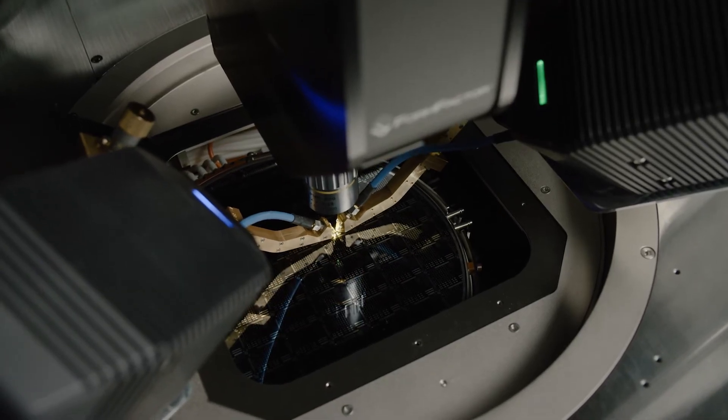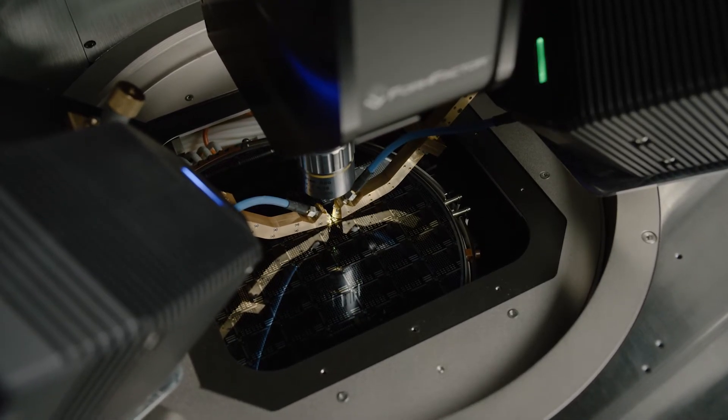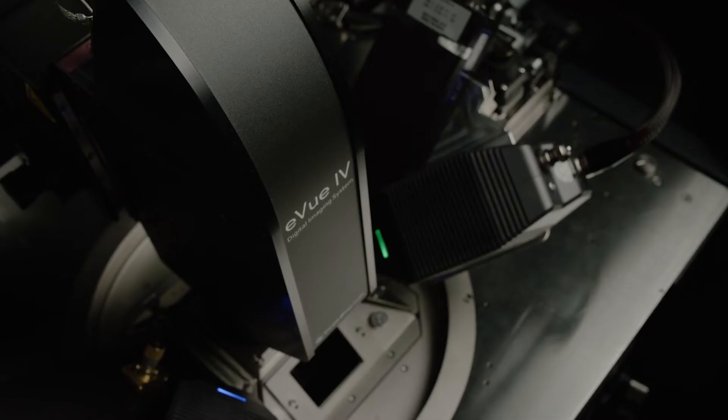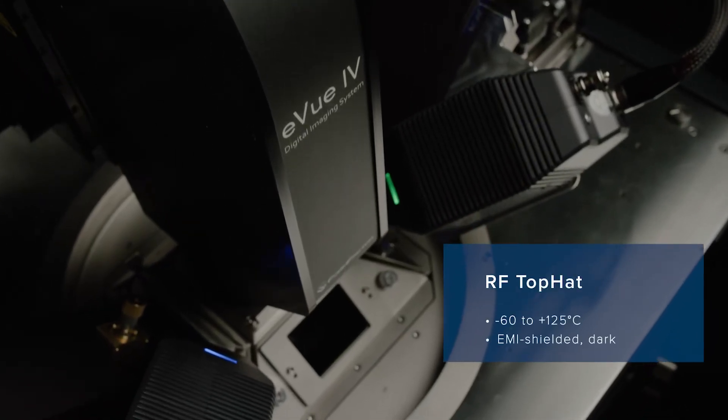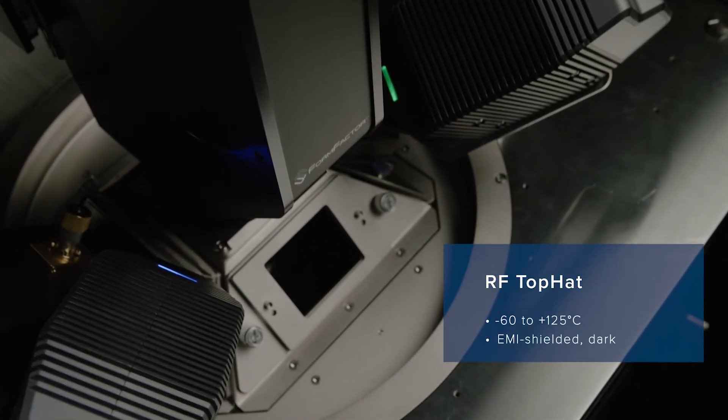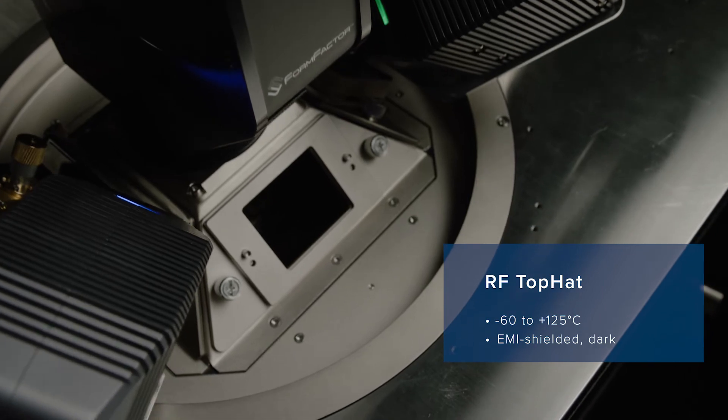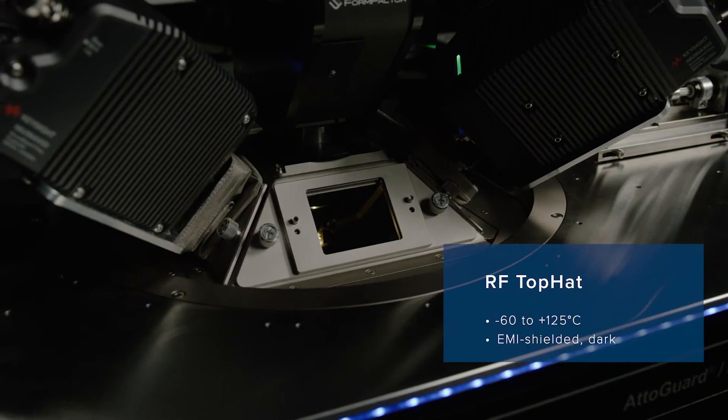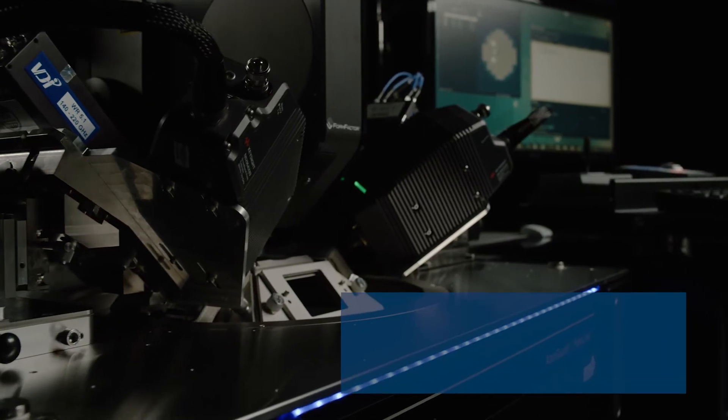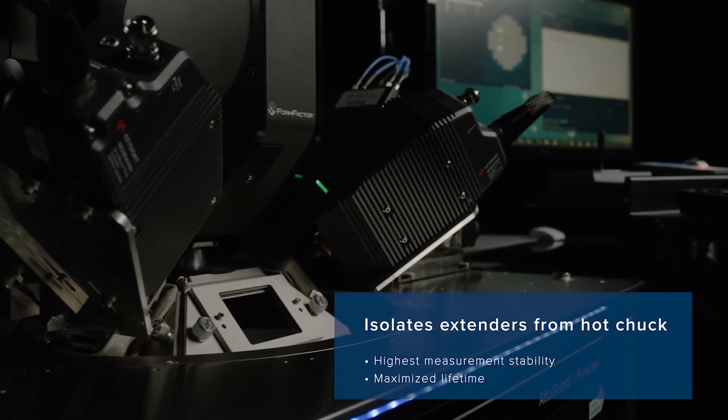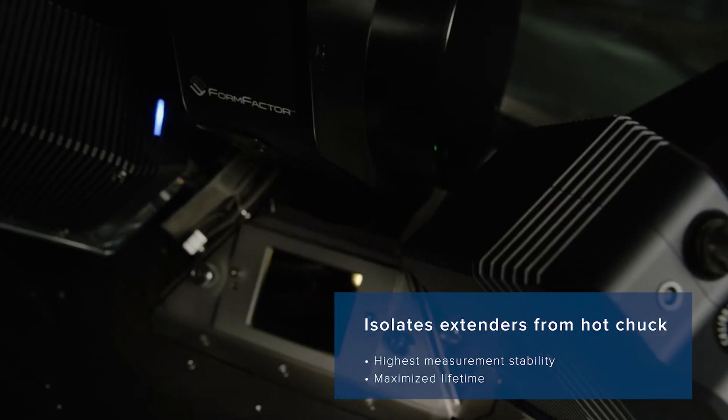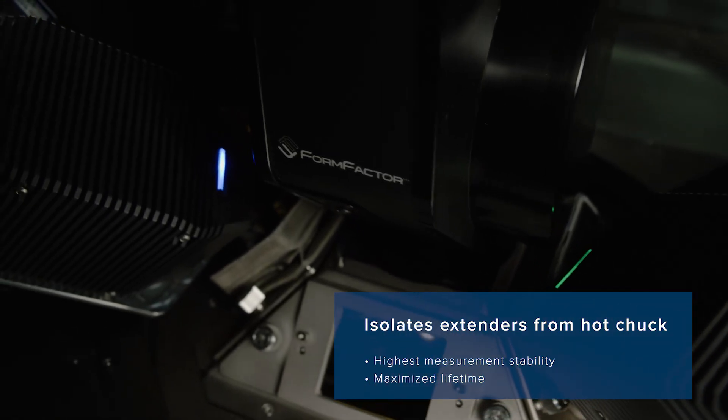Equipped with FormFactor's patented RF top hat, the solution has full thermal range, EMI shielded, and dark measurement capabilities. The RF top hat isolates the sensitive extenders from the hot chuck, which ensures highest measurement stability and maximizes their lifetime.